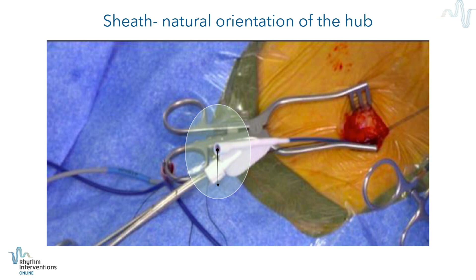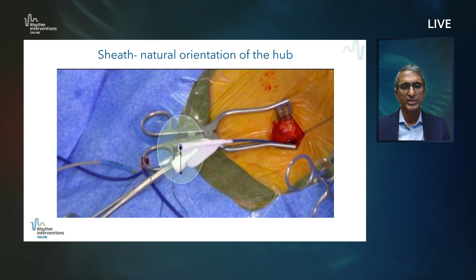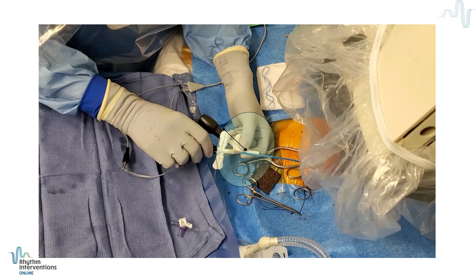In a C315 His sheath, the hub of the catheter is pointing at 6 o'clock. That is the traditional home position. And if you want to advance the sheath more towards the ventricle, slightly rotate the sheath clockwise and advance the lead and the sheath. In a deflectable sheath, that orientation is slightly different. It's at the 9 o'clock location, and similar clockwise rotation will get you across the valve towards the ventricle.